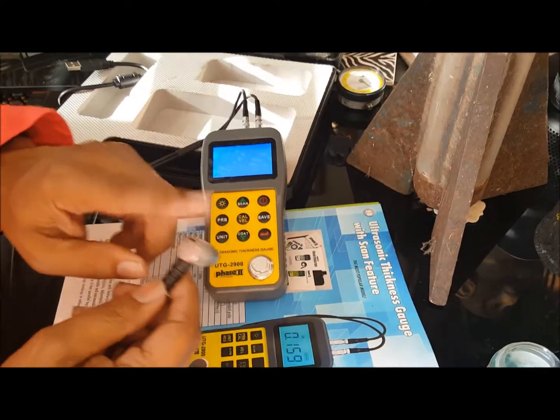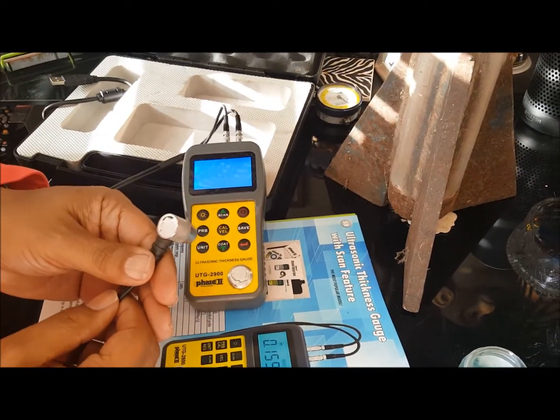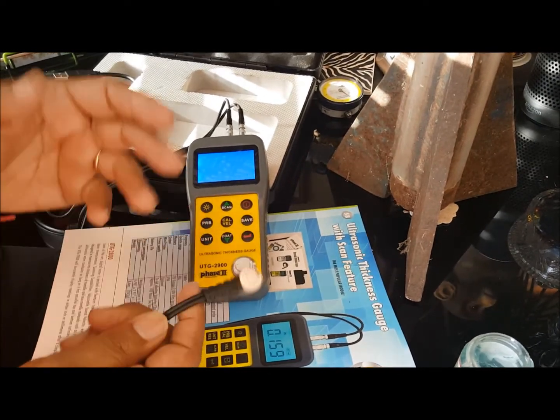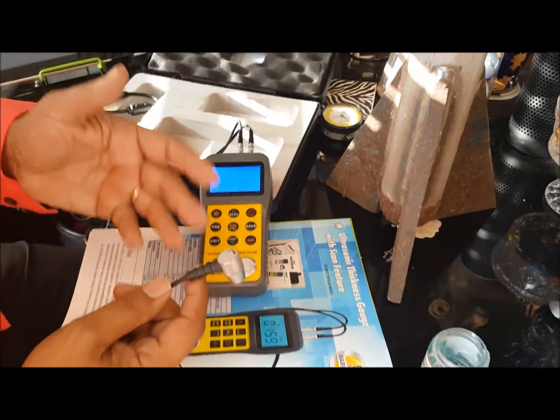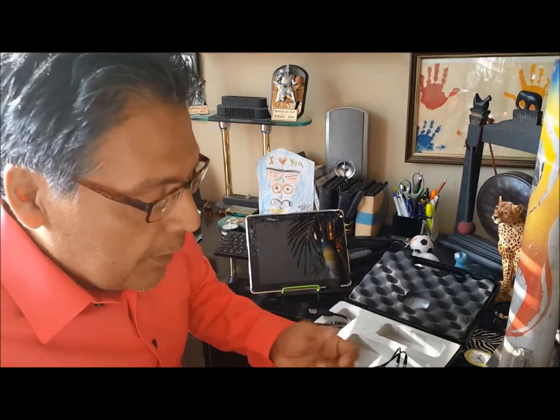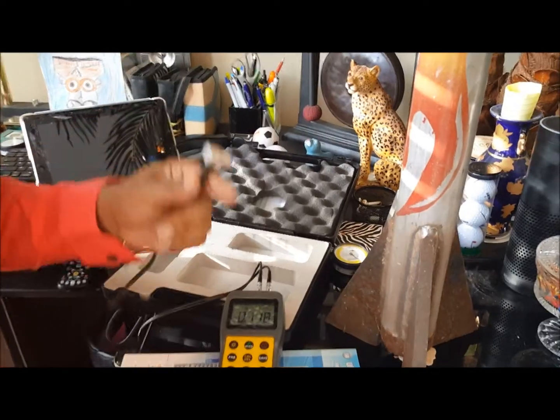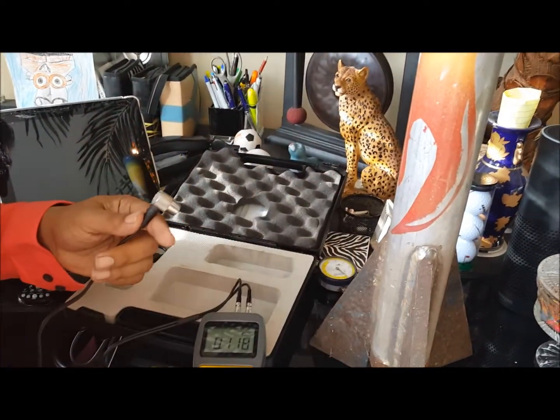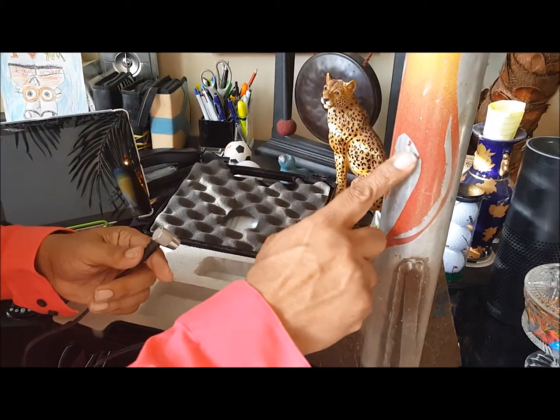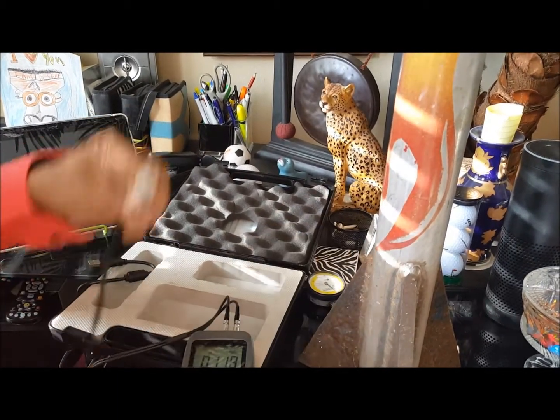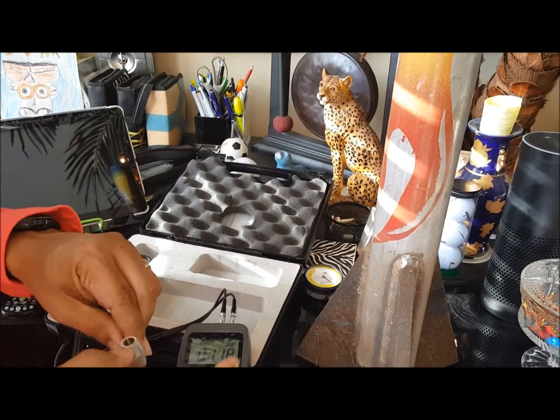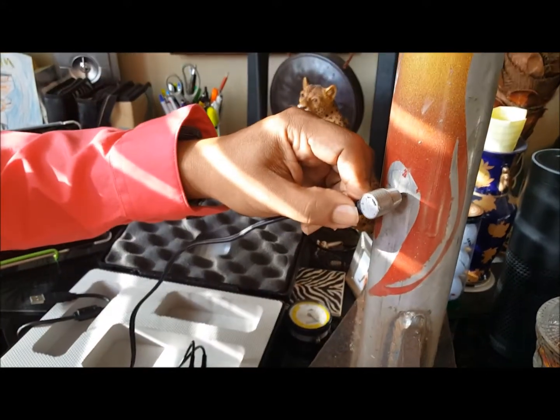There are different transducers as well. This particular one is 5 megahertz, but depending on the application, there are transducers that will handle it. If you have a really hot surface, thin pipe, or aluminum, we have the solution. So let's take a thickness on this piece, this bottle rocket launcher. We'll put some gel on there, put the transducer up against it, and see what we come up with.